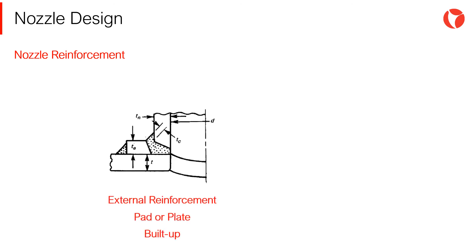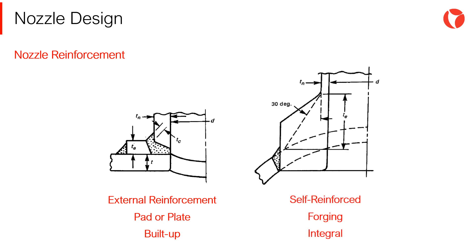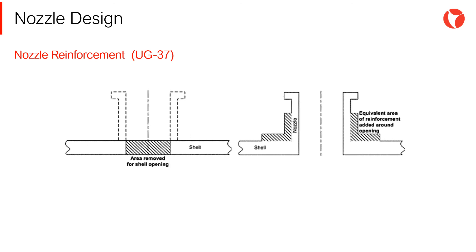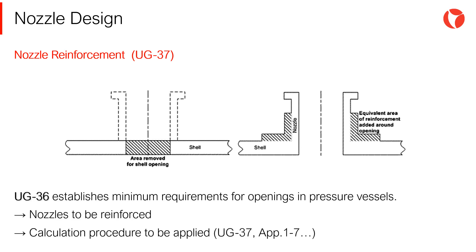The most common approach is to use pads or plates as an external reinforcement element. In some cases, mainly due to safety reasons, it is necessary to minimize the number of welded joints in a vessel; in these cases, self-reinforced nozzles made out of forged elements are used. The ASME code establishes the places where reinforcing material should be provided for the different nozzle configurations. Minimal requirements for openings are laid out in paragraph UG-36, which first defines which nozzles must be reinforced, then states which calculation procedure is to be followed.